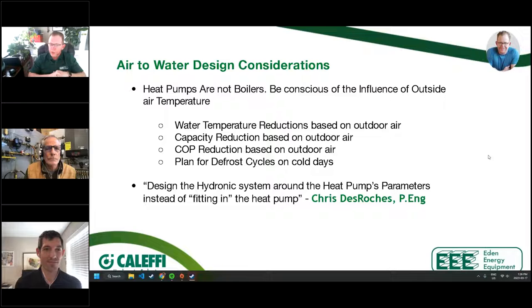And then the other thing that comes into play is we need to design around the defrost cycle. I don't mean to be overdramatic, but we have to be aware there is a defrost cycle, and that defrost cycle is going to be quite significant. Max is going to talk about it. So we need to make sure we're aware of that and understand what's happening during that defrost cycle and how it could impact our ability to heat the space. The good news is, in a hydronic system, it's not going to be as serious as it might be in another system, because we've got things in play, including a buffer tank. They will give us a buffer of energy so that when the outdoor unit is in defrost, we don't need to worry about it so much. But this is, again, why all three of us are pushing aggressively for buffer tanks, in some cases against what some manufacturers are saying, because we're coming at this from an engineering perspective.